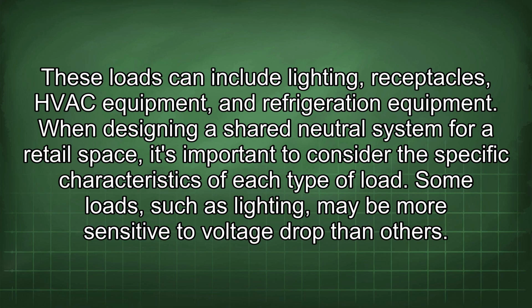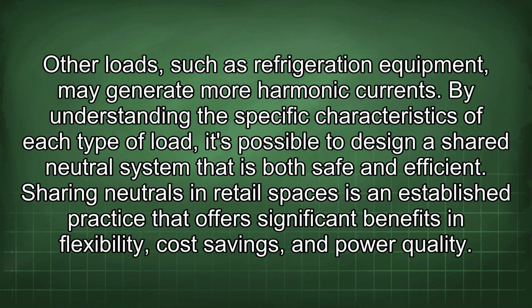When designing a shared neutral system for a retail space, it's important to consider the specific characteristics of each type of load. Some loads, such as lighting, may be more sensitive to voltage drop than others. Other loads, such as refrigeration equipment, may generate more harmonic current. By understanding the specific characteristics of each type of load, it's possible to design a shared neutral system that is both safe and efficient.